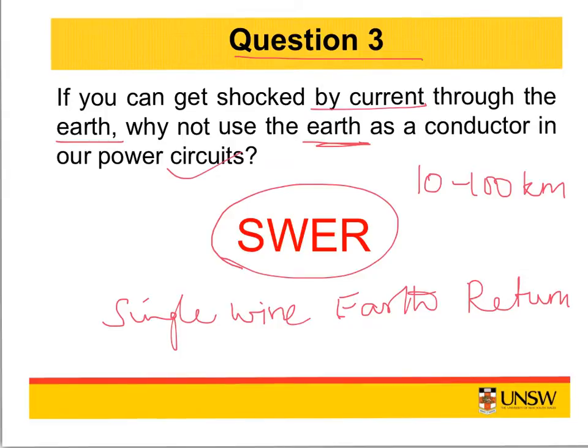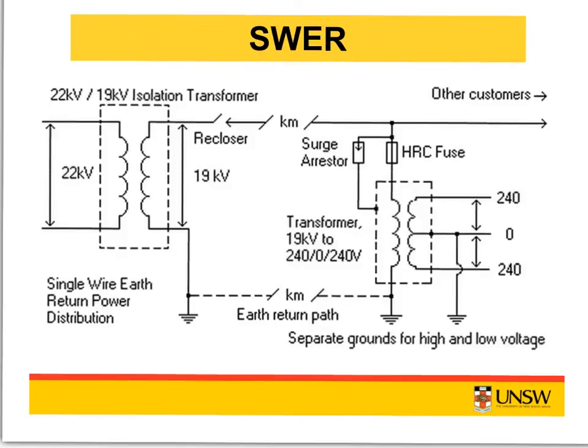There is over 190,000 kilometers of SWER currently in use in rural areas of Australia. Compared to conventional lines, SWER is equally safe, more reliable, less costly, but with slightly lower efficiency and restricted load capacity. Separate earthing for function and safety are used in this system. Okay, so this figure shows a typical SWER system. So you can see here the power is supplied by means of an isolating transformer.